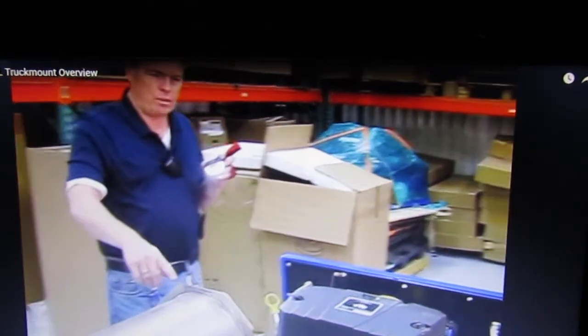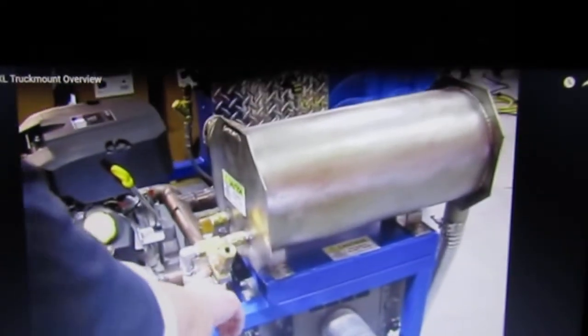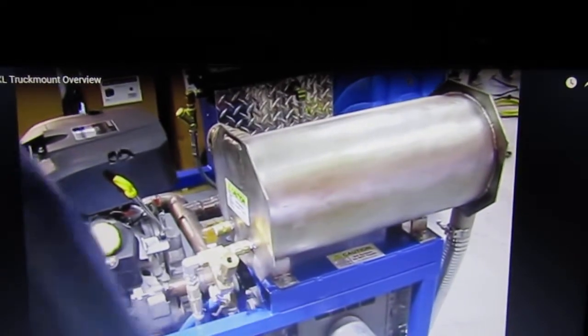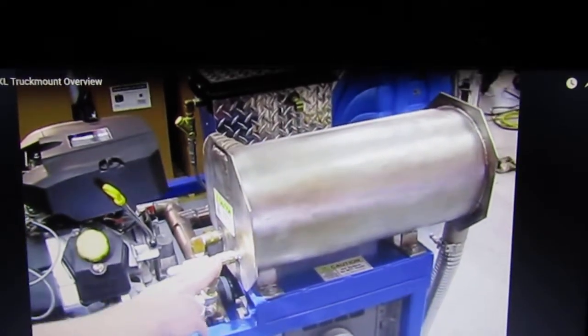Also on this side of the machine, you'll see some more fittings. This is a 2000 PSI pressure relief valve, and what that is designed for is to prevent overpressurization of your heat exchanger, which will help save it. You have to realize that the air coming out of the engine is 1200 degrees Fahrenheit, and your water in here is typically going to be around boiling.